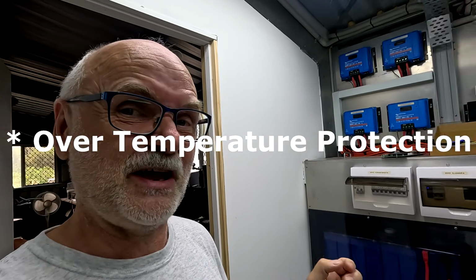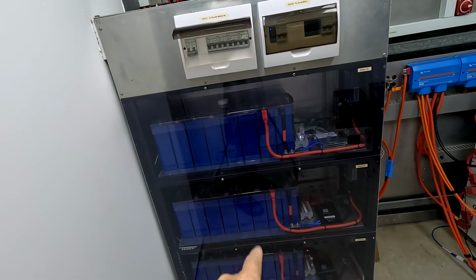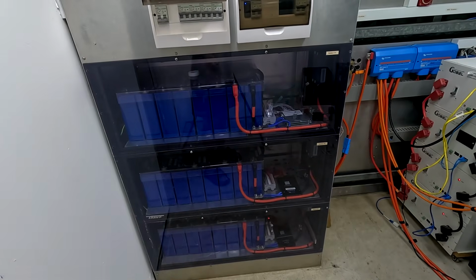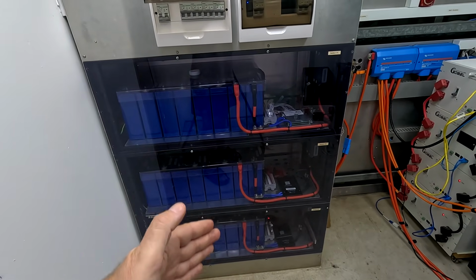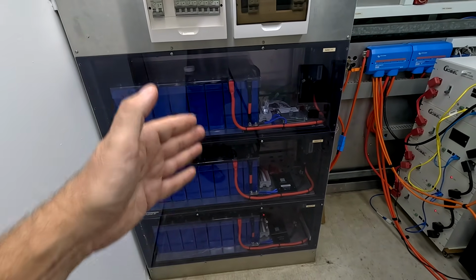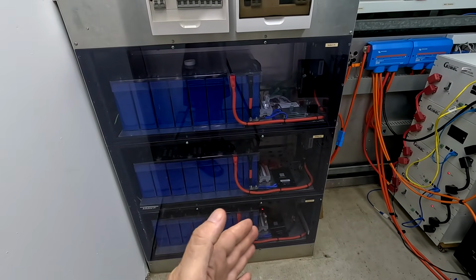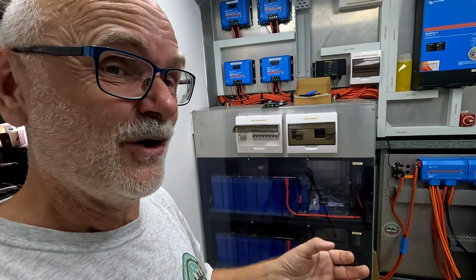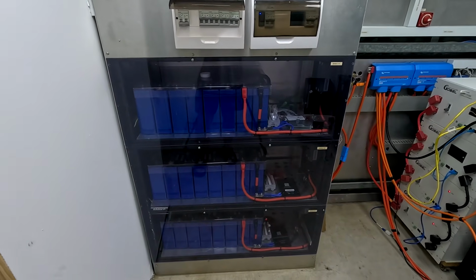And I have one put in between the batteries, and the other one sits in the back side of the circuit breaker. And during summer I have charged here with 15 kilowatts or something into these batteries. This was like 270 amps, and the circuit breaker got pretty warm. So it triggered an over voltage protection for one of these batteries here. BMS turned off, and these 270 amps then split into two and went into these two batteries, just to create an overcurrent protection in each of these batteries, and eventually the whole system shut down, of course, while I was not home. But now I'm still running this with no communication.